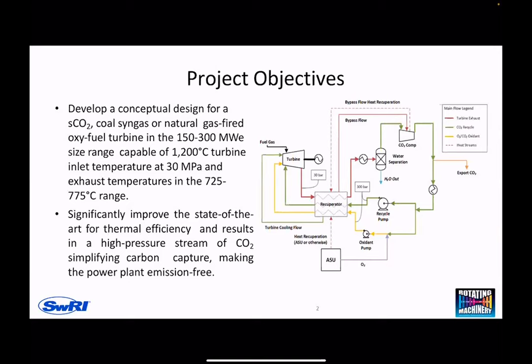This turbine, instead of a 3-to-1 pressure ratio, is a 10-to-1 pressure ratio—coming in at around 300 bar and exiting at 30. That's why this cycle doesn't involve just a single compressor; it involves a vapor compressor plus a liquid or supercritical CO2 pump. So multiple stages of compressor, multiple pumps, and a single turbine to generate this power.